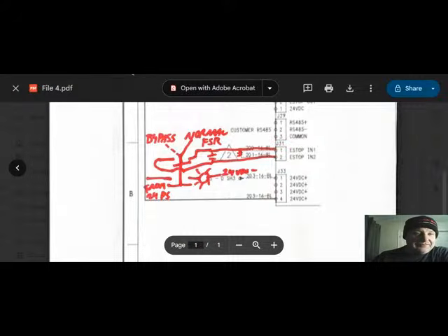Again, doesn't even have to be a light. Could be an input into the customer DCS that there's a warning up on their computer screen saying, hey, this fire suppression relay and the compressor's been bypassed. Could be a warning light in the maintenance office. I mean, it's literally, again, because we're supplying this contact and it's a dry contact, so whatever power we bring in from wherever, that power can travel back out to wherever we need it to go. You're pretty much limited by your imagination on that one.